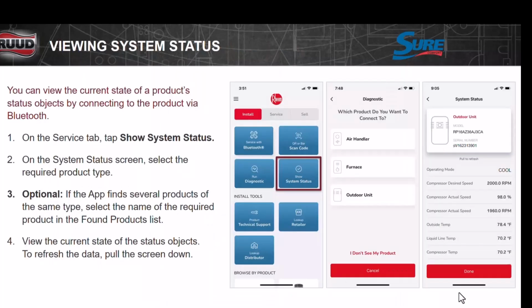Let's go into the system status screen. We've gone through the Bluetooth setup, and we've gone through some diagnostics. We're at system status, so let's look at what the system's doing. We log into the unit, go to status. Now we see our air handler, our furnace, and our condenser. Now we can see what's going on.